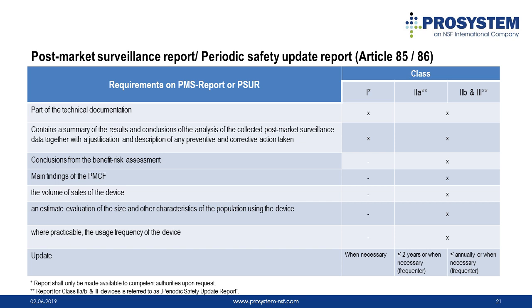In addition, for Class 3 and Class 2B implantable devices, the report should be submitted in the EUDAMED database and will be assessed by the notified body annually. For other devices, the report will be assessed by the notified body upon request. However, when any new information is received which may have an impact on the existing documentation, you must update your report immediately.